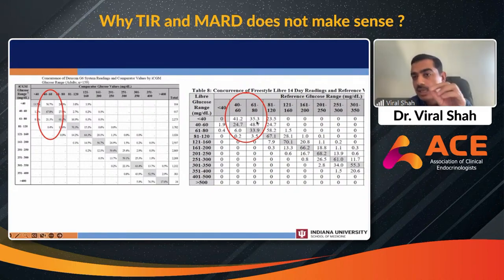This is a FreeStyle Libre 14-day system, Libre 1 system. Look at that 40 to 60 milligram glucose value. It's at 24.7% of the time it's going to say 40 to 60 milligram per deciliter. Okay, remember that part. But 41% of the time, look a little bit higher, 41% of the time it's going to say less than 40 milligram per deciliter. So what it means is it's biased towards hypoglycemia. It is telling you lower than what you actually are.